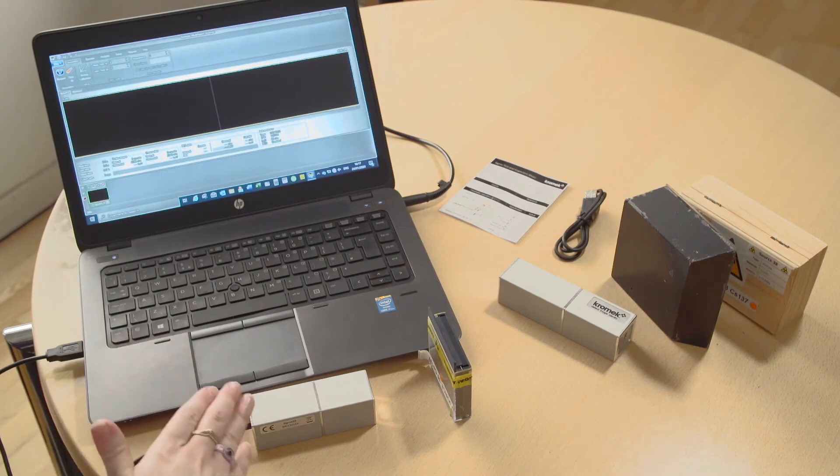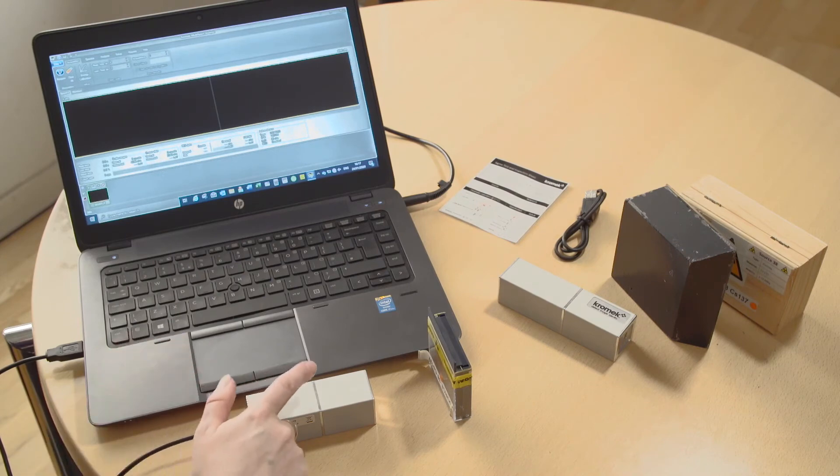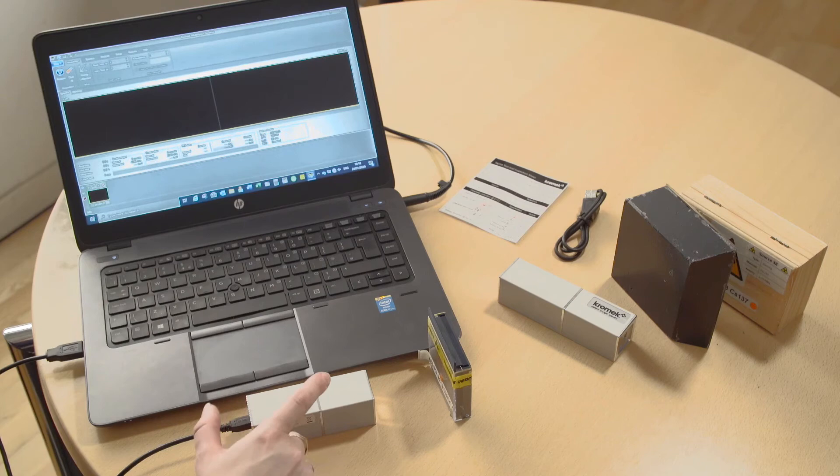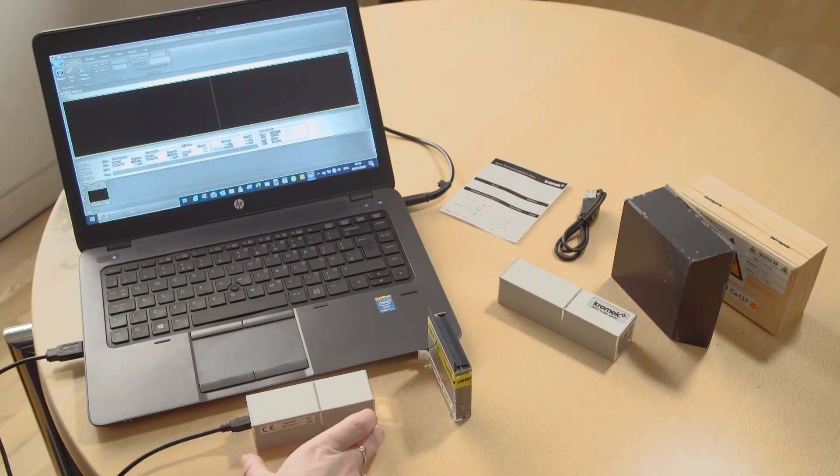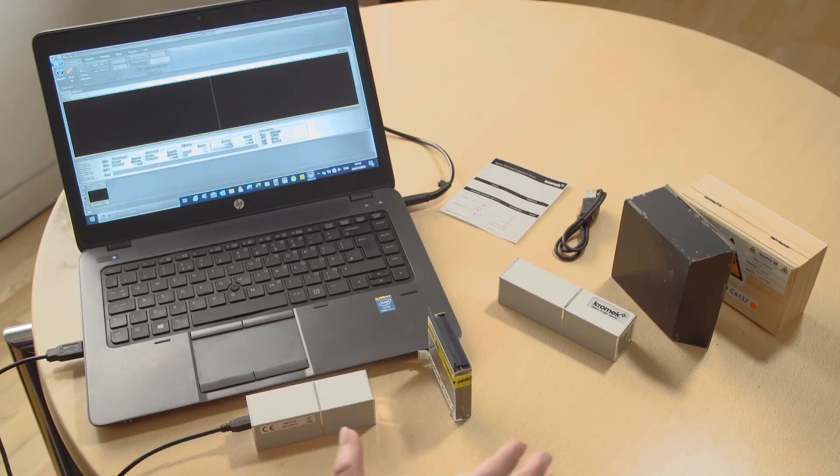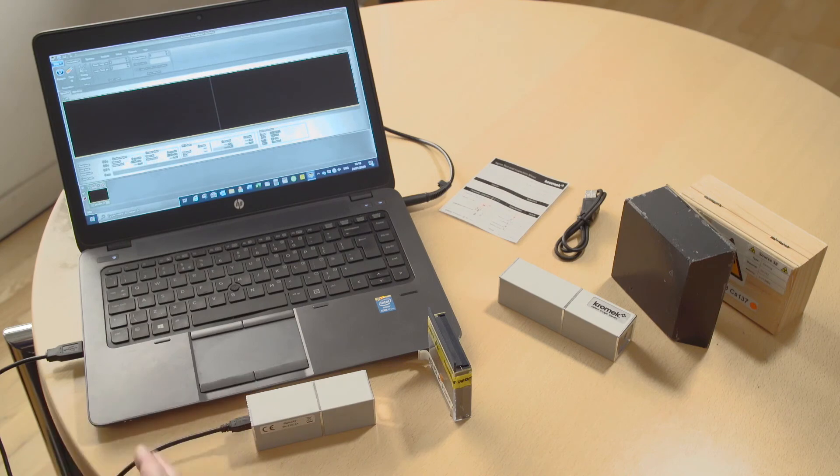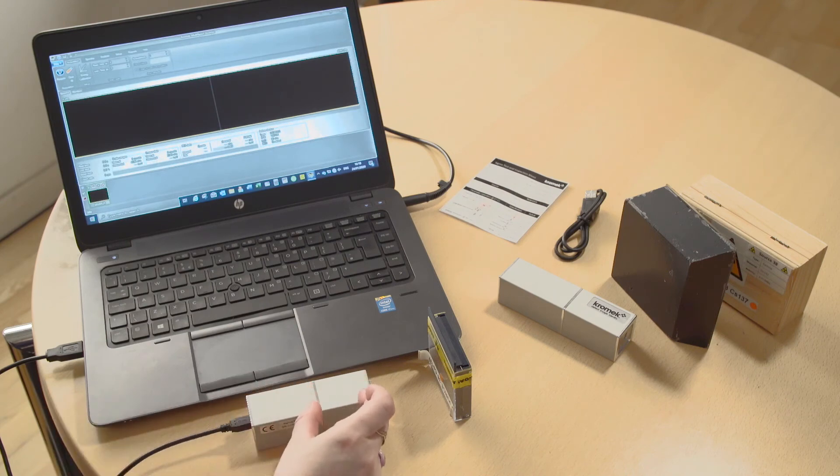So the Sigma 25 has a 1x1x1 inch detector and this unit is quite good for when you are in high flux environments because it has the smaller detector.